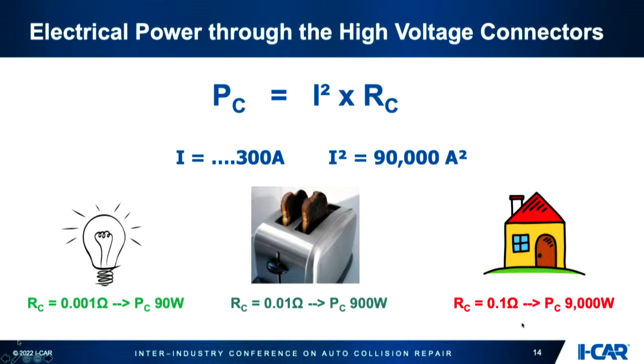At 1/10th of an ohm, now you're at 9,000 watts, which is basically enough to power your entire house. So now you have all that heat in one connector, and that's where a fire can start, just from overspray, dirt and grime getting in there. You may not even be able to see it, but that fine mist can cause resistance to go up substantially.